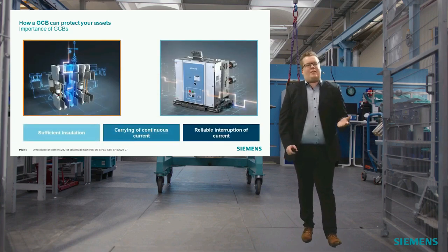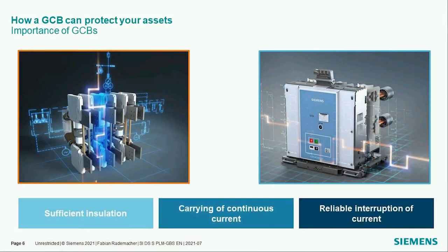Now you may ask: on the one hand we have the IEC circuit breakers for distribution switchgears, and on the other hand we have the heavy duty switchgears such as generator circuit breakers or circuit breakers for arc furnace applications, but I only want to highlight the generator circuit breaker. They all have the same task, which is, first of all, sufficient insulation. We have to fulfill that there is no discharge between the phases.